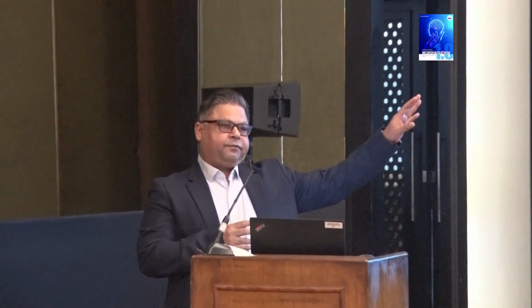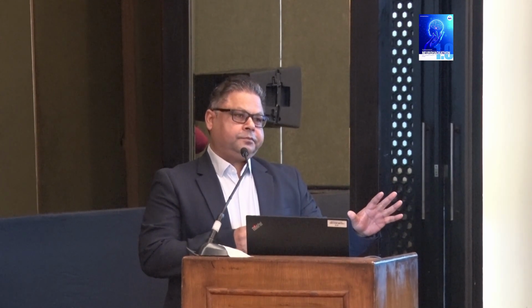For the benefit of everyone, can you elaborate on how you say it is 6F and then it is 8F and the inner ID is more? Can you elaborate on the compatibility with the guiding catheter and the femoral sheath, which sheath should be used? As I showed, on the packaging itself it says 8F. 8F is the outer diameter. It's a 6 French sheath with 8 French of outer diameter. So if you have to place a short sheath, it will go through an 8 French sheath. And the inner ID is 090.